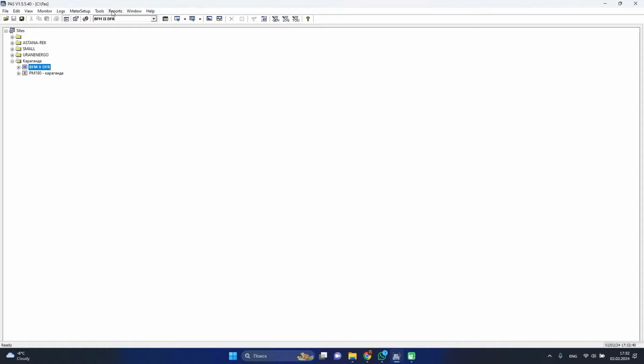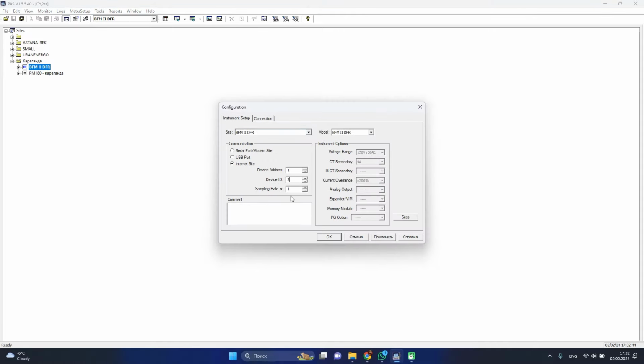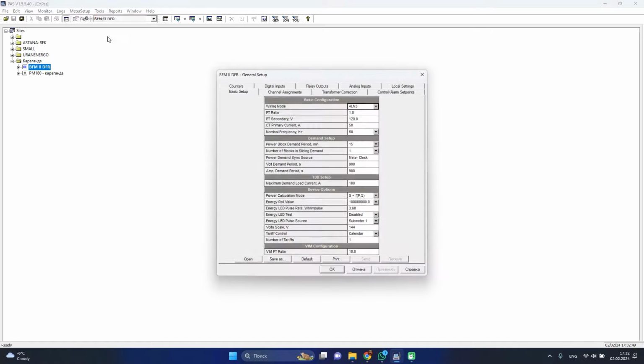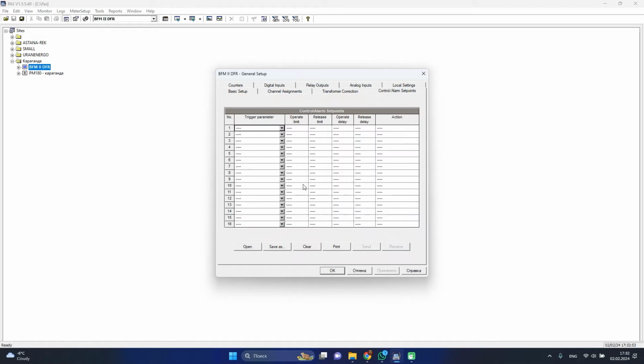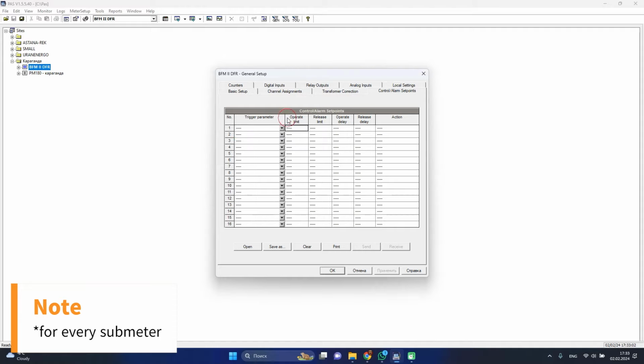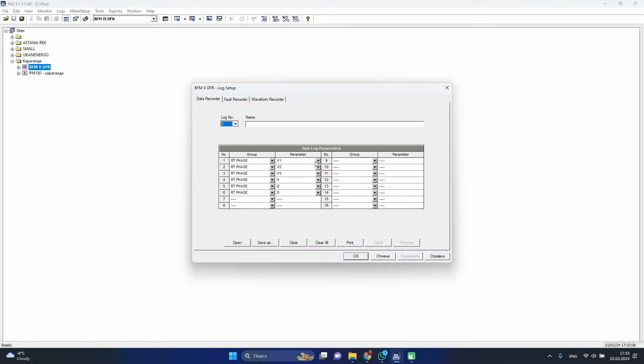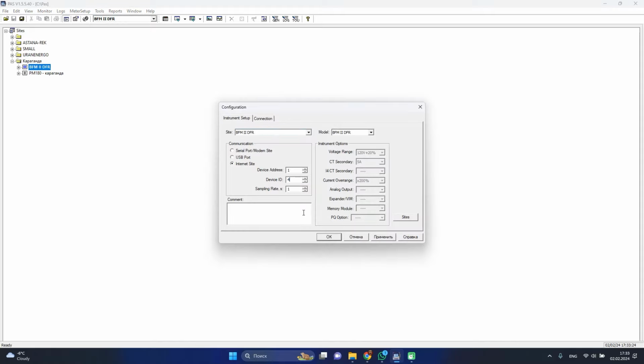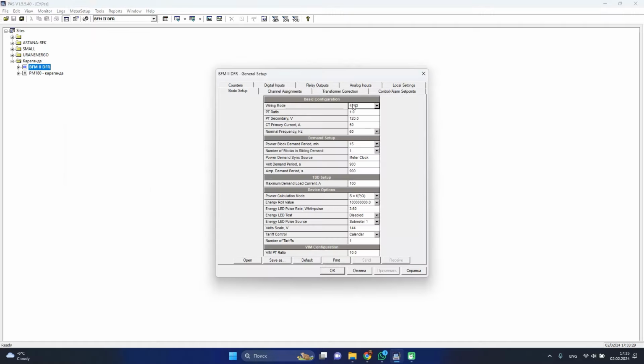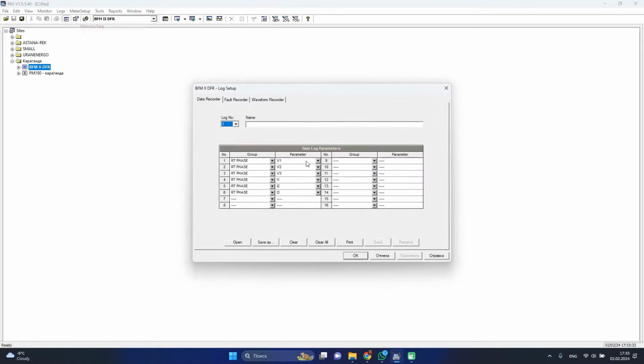But I want to show you more about the submeters. To change the submeter, we need to change the device ID. And for every submeter, we have different kinds of set points. They are different for every set point. We can change the trigger here, and also we can change the memory log for every submeter. We can write about 16 parameters in the memory of this device. And let's change it again. Yes, and we have here another set of set points, and if we had this online device, we would change this data log parameter.